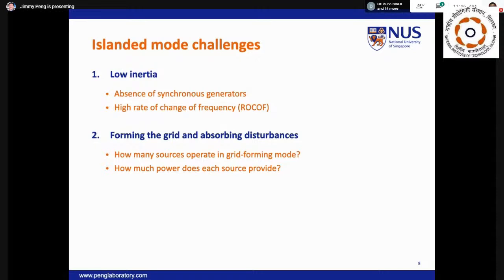A typical microgrid will have a rate of change of frequency in the range of a few kilowatts per 0.1 hertz. Whereas if you look at the US, the Eastern interconnection has 2,760 megawatts per 0.1 hertz drop, or 1,482 megawatts per 0.1 hertz drop for the Western interconnection. So typical monitoring, analysis, and control philosophies of running a power grid may not be suitable for a microgrid scenario.